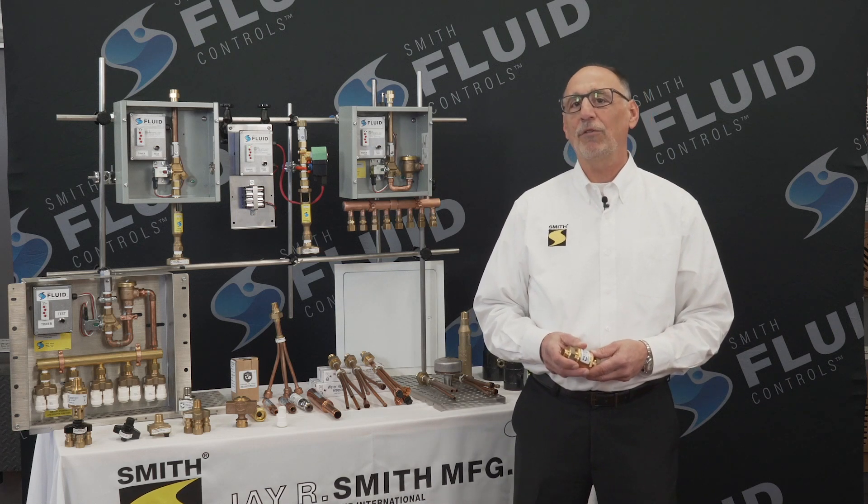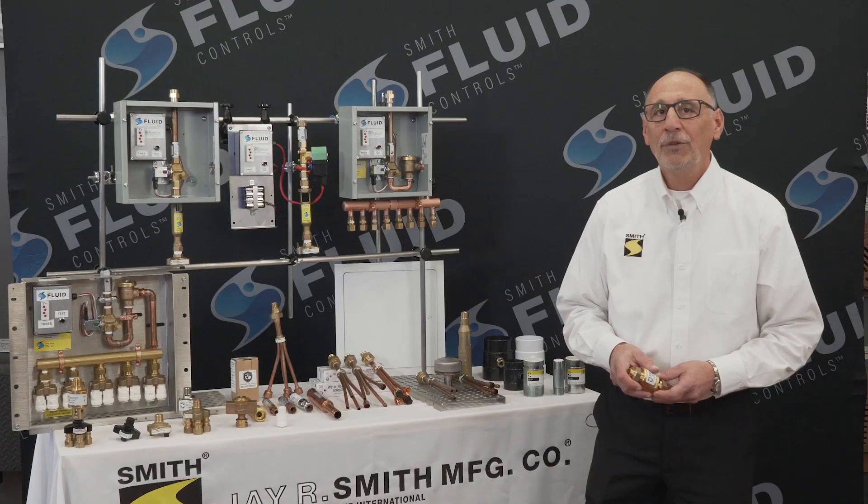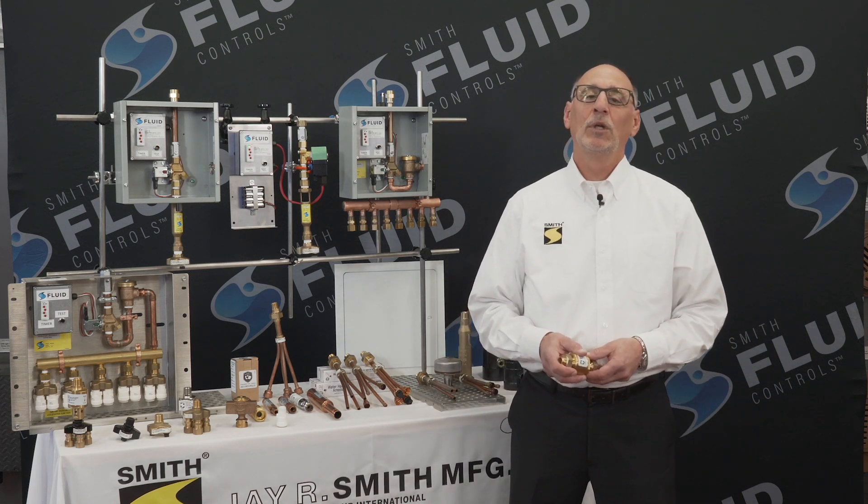The 3 psi variance for activation is the lowest activation for a pressure drop trap primer on the market. The Trap Defender operates between 20 and 80 psi with a minimum pressure drop of 3 psi and virtually no moving parts inside. The phenomenon that creates friction against pistons and O-rings in competitive offerings increases the risk of failure due to moving parts and hard water. The lead-free Trap Defender works by pressure created inside the body compressing a Buna sleeve that is more sensitive to atmospheric pressure than a piston O-ring.